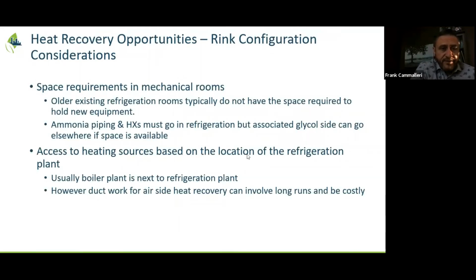Something to keep in mind is that the rink configuration matters a lot in terms of the viability of these heat recovery opportunities and their financial viability. A lot of these heat recovery opportunities need some space requirements, and we're finding that older refrigeration rooms typically don't have a lot of space. We found a lot more space in newer facilities. So there might be space constraints you have to deal with, which can make the whole initiative either not doable or very costly.